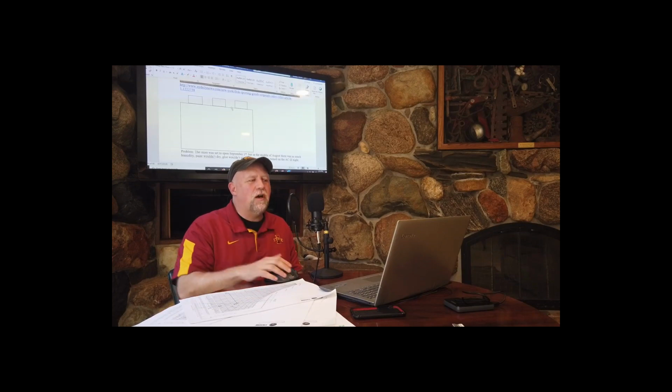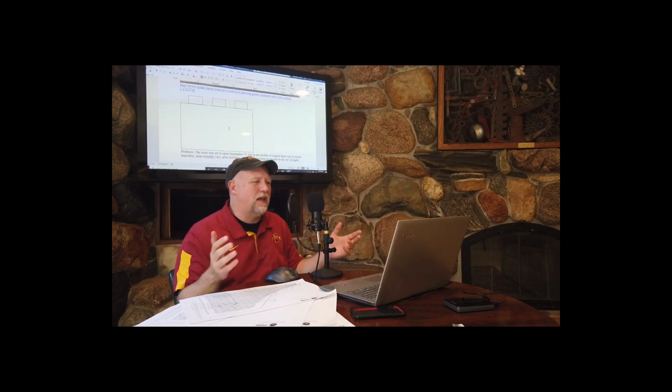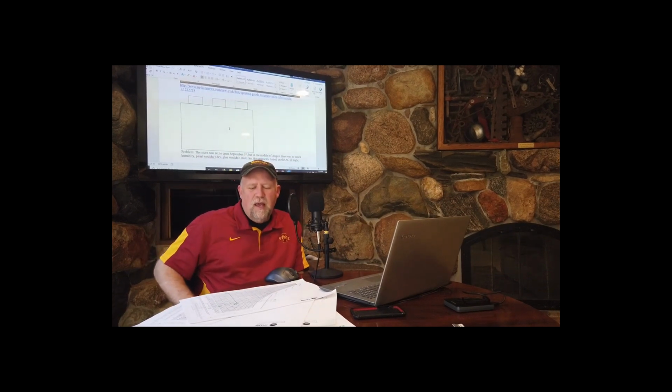All right. So after you paused and you thought about it, let me tell you the answer. What happened is, if you look at a big box store, and a Dick's Sporting Goods is just like a Walmart, just like a Target, just like a Sam's Club, just like all of them, we have one big room and a whole bunch of rooftop air conditioners. And they turned all of them on, and they probably set it to about 75 degrees. Take a look at your psych chart. What happens when you go from 95 degrees, 50% relative humidity, straight over to 75 degrees?